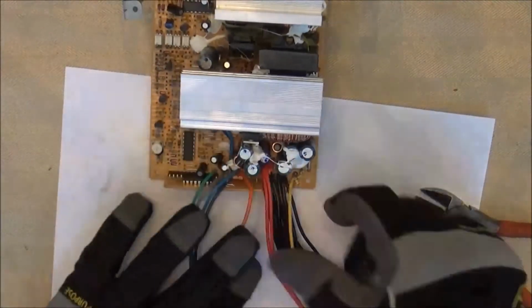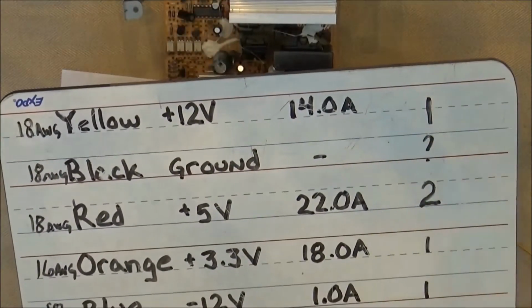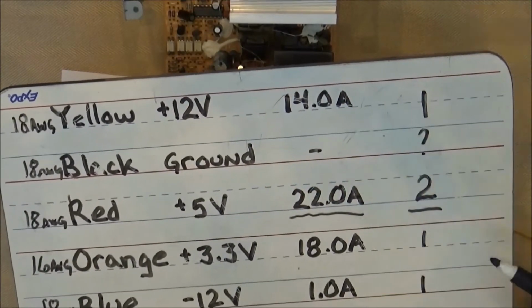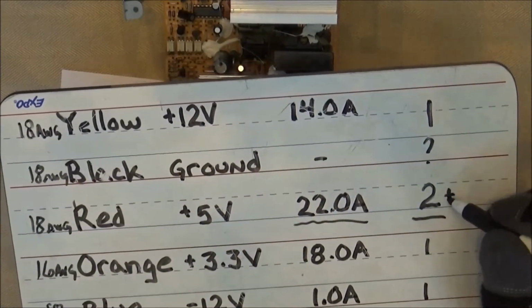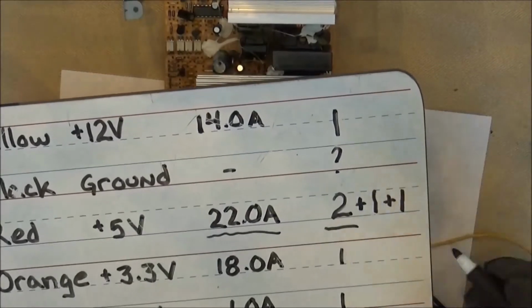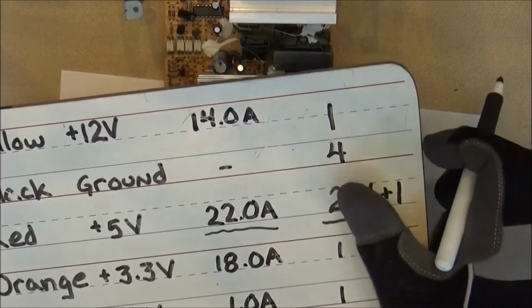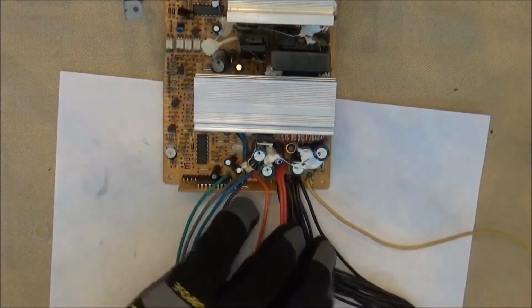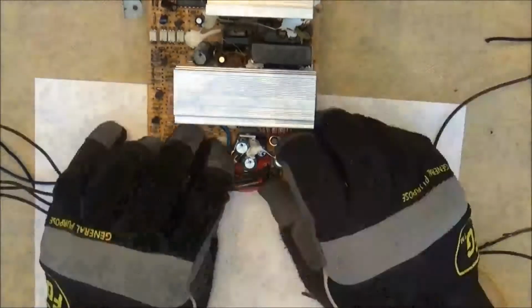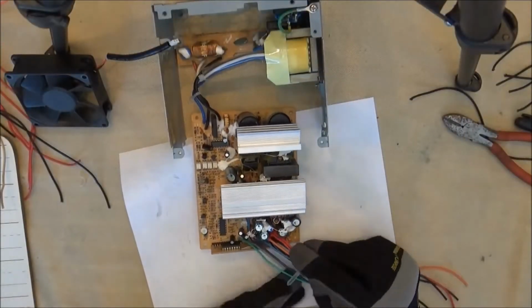Now we must take a look at the ground and calculate out how many we need. So the ground, what we need to do is look at the maximum conductors of any particular color, which is 2. And I'm going to need one for the switch, and I'm going to need one just in case I want to add something later. So I have a total of 4 ground wires that I need. So here I've removed about 15 ground wires.